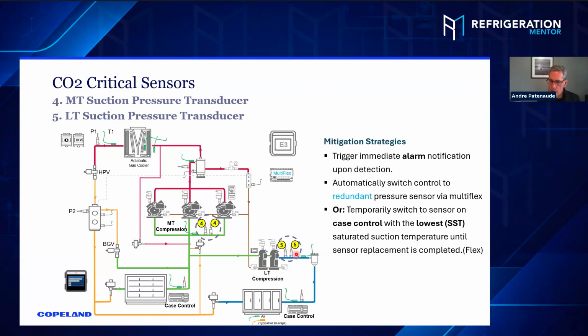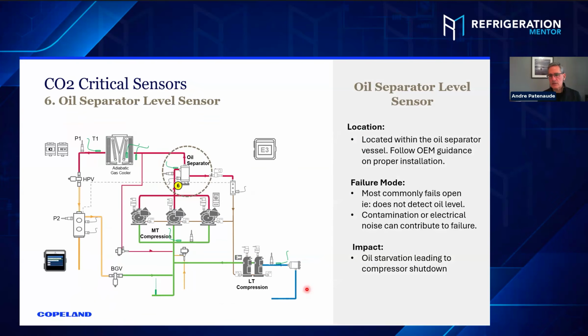If you get a failure and you don't have a redundant sensor, you go to that sensor, which obviously has to be the lowest SST one, to limp along. Okay. Yeah, and that's usually done through like 2 or 3 degrees different than the actual header. So you go to the lowest one for sure. Yeah. So that makes sense. And that would be easy to set up. You've got to go to the refrigeration schedule. So you look on the refrigeration schedule, you look at all your cases for your low temp, and then you'll just find either the low temp walk-in box or the low temp coffin case. It's going to say right on there which one's your lowest, and you pick that case, pick that sensor. Yeah. Perfect.